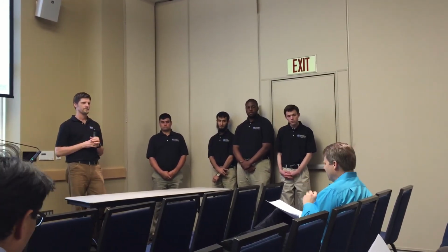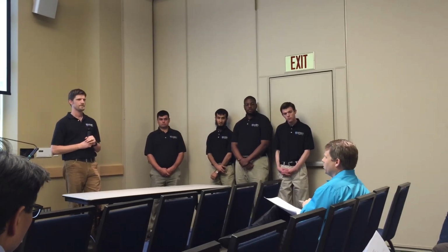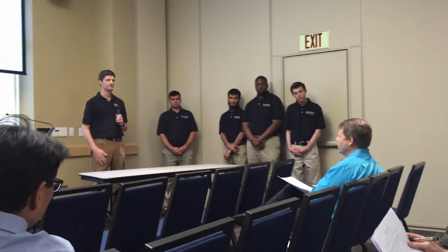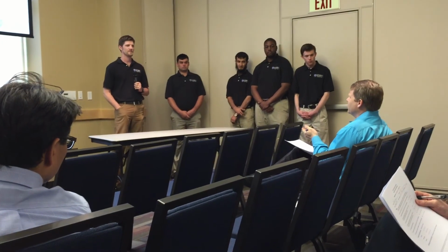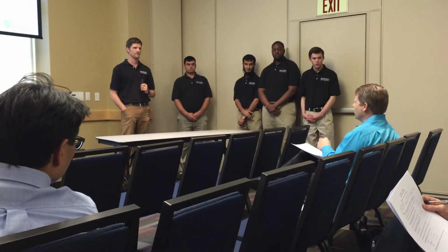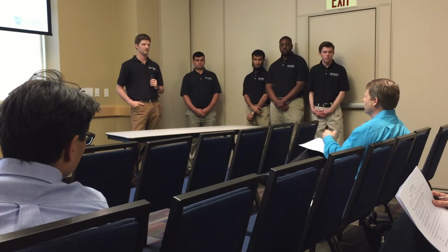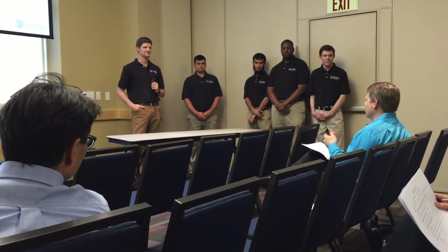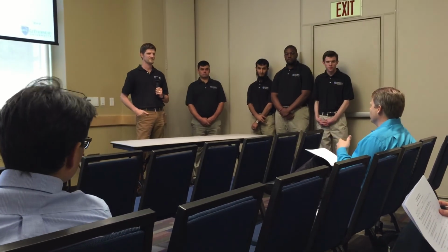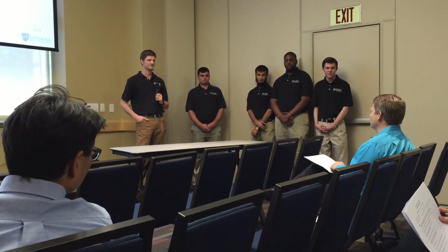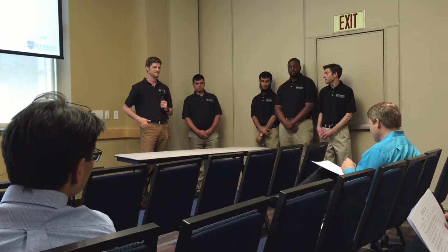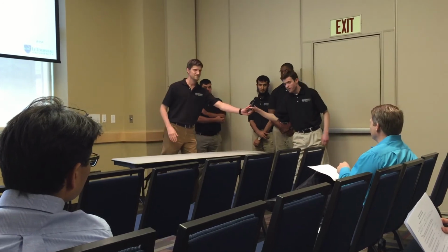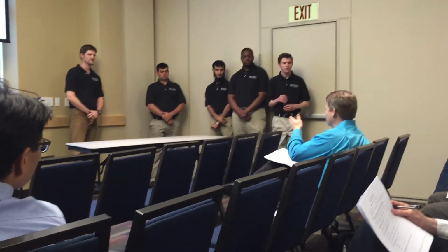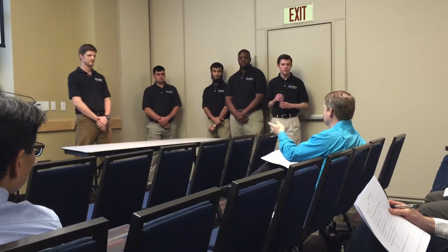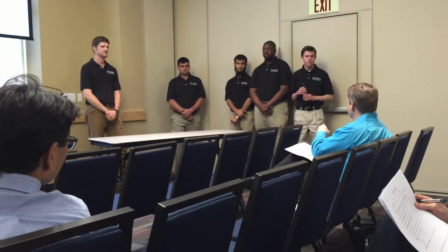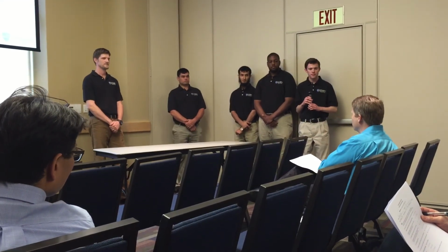And the last part of that question was from a software perspective. I noticed when you started there's very little feedback in terms of test operation. Normally when I design something from a software perspective, I like to show that I'm making progress, so somebody doesn't throw it at a wall thinking it's broken and just keep waiting. Part of that software would also normally deal with unit calibration, going back and testing a known sample between runs, and possibly compensating for temperature.